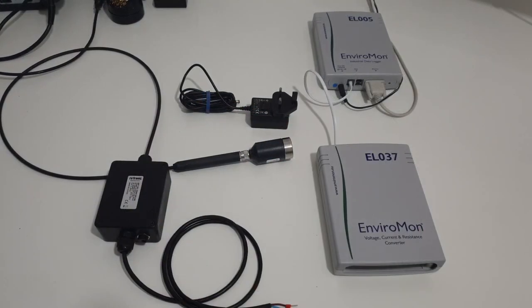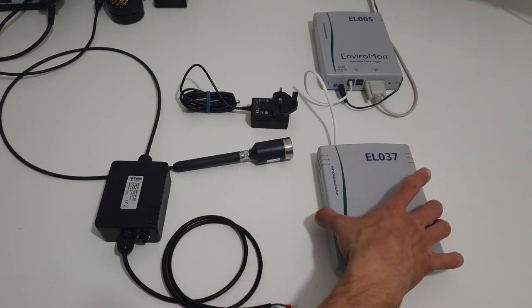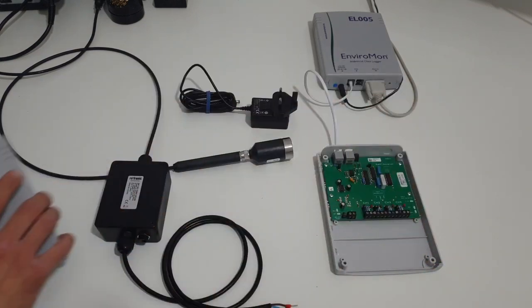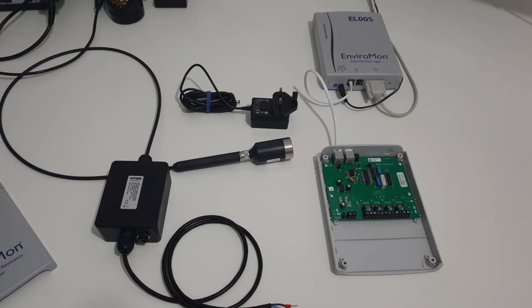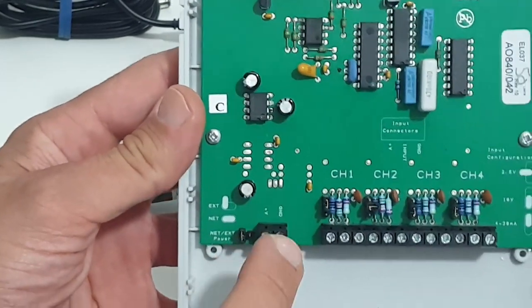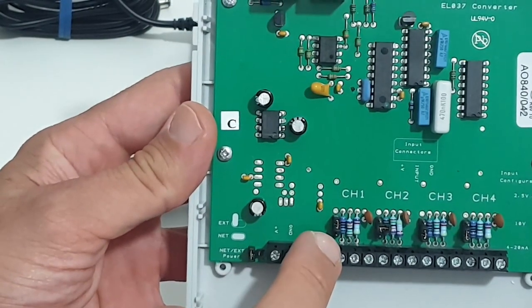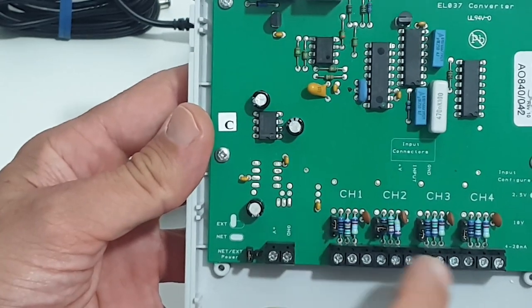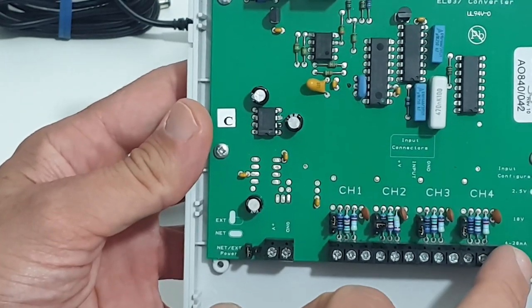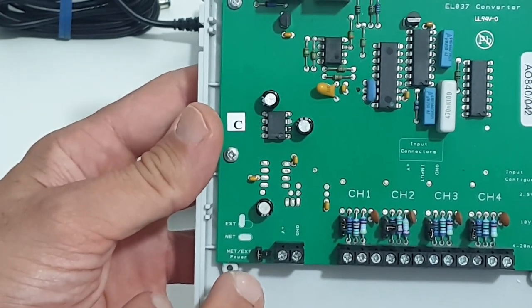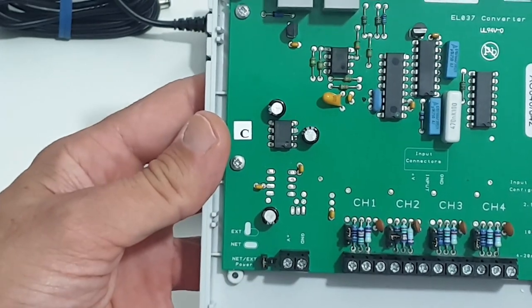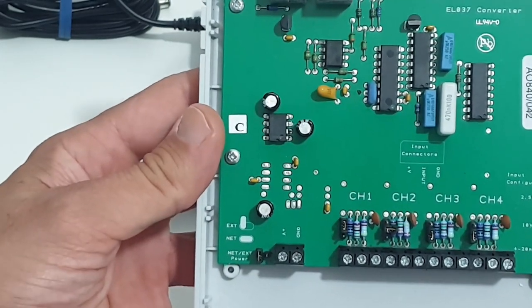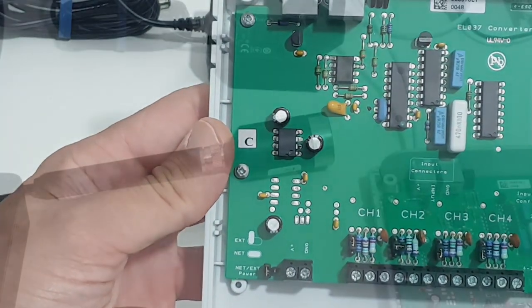So we'll now connect everything up. The first thing we need to do is take the cover off the EL037. The next thing we need to do is ensure that channel one is set to 4 to 20 milliamps. You'll see that the jumper is on the first two pins over there, which is 4 to 20 milliamps. And we don't need to bother with the power over here because the transducer itself has its own power supply.